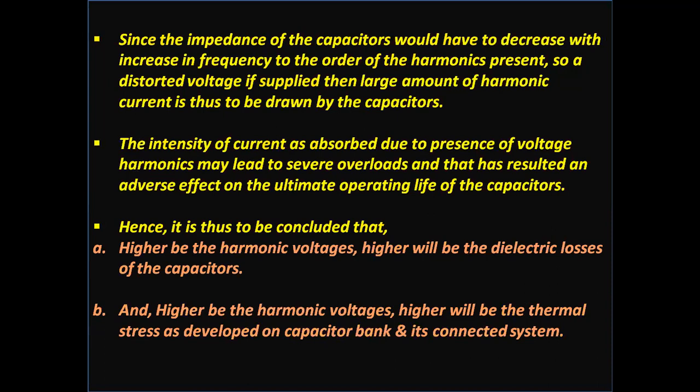Since the impedance of capacitors decreases with increase in frequency — to the order of the harmonic frequency present — a distorted voltage, if supplied, causes a large amount of harmonic currents to be drawn by the capacitors. The intensity of current absorbed due to the presence of voltage harmonics may lead to severe overloads, resulting in an adverse effect on the ultimate operating life of the capacitors.